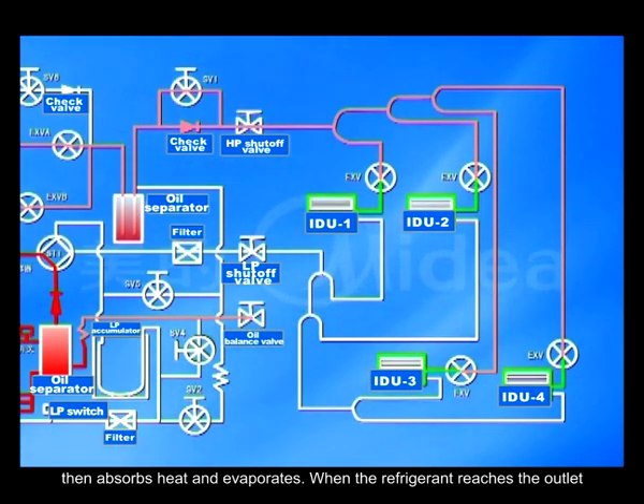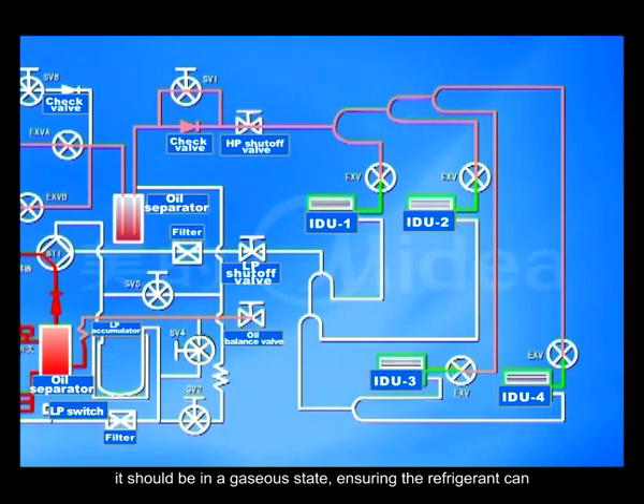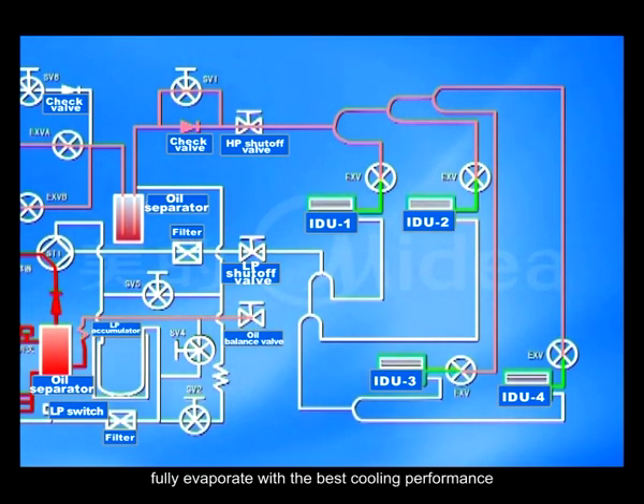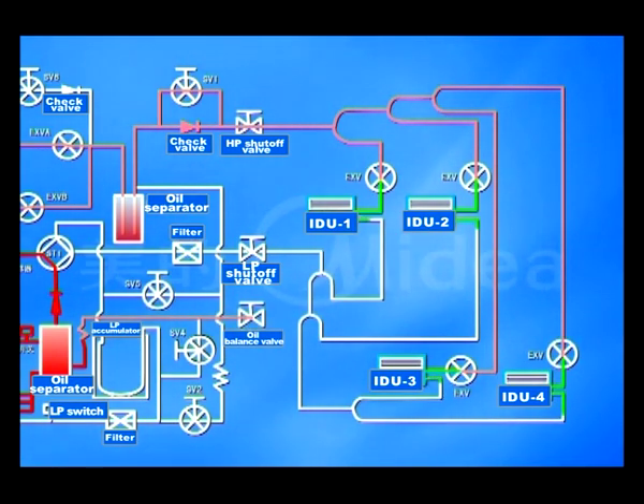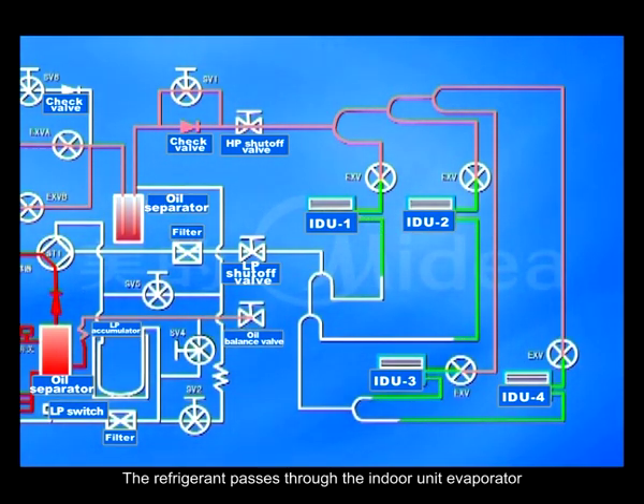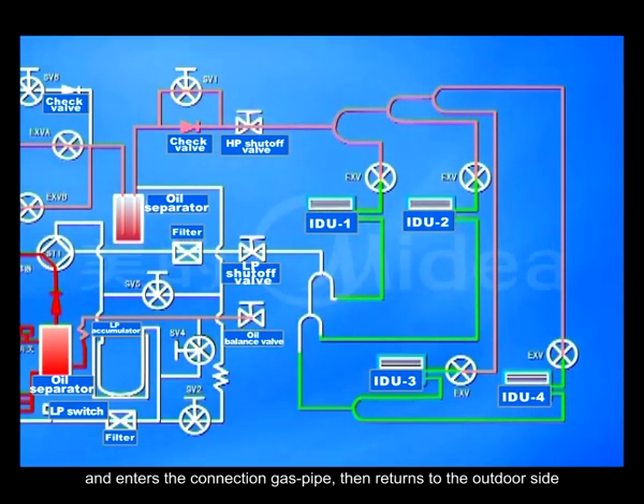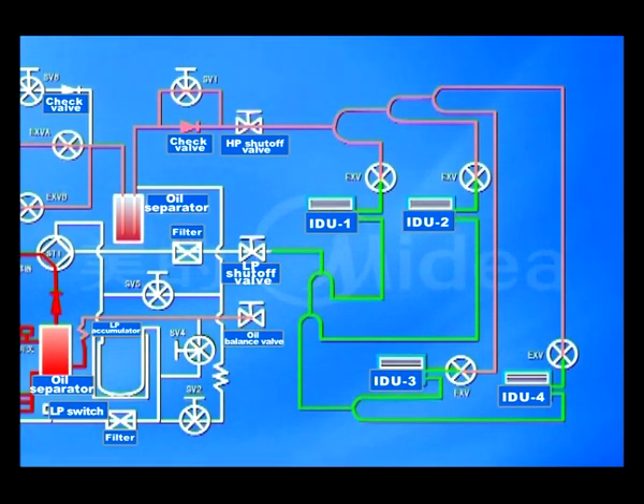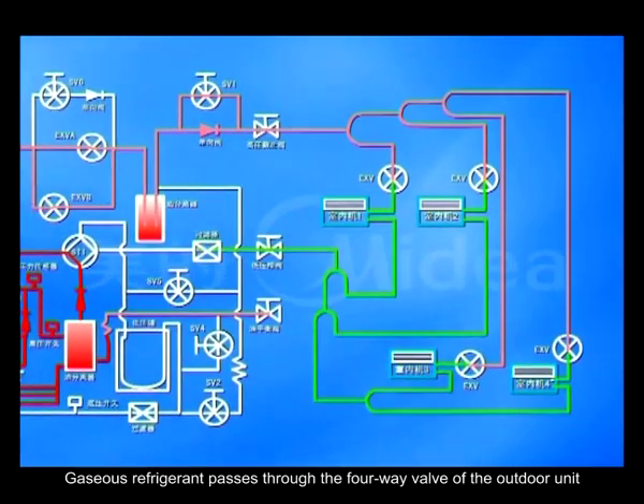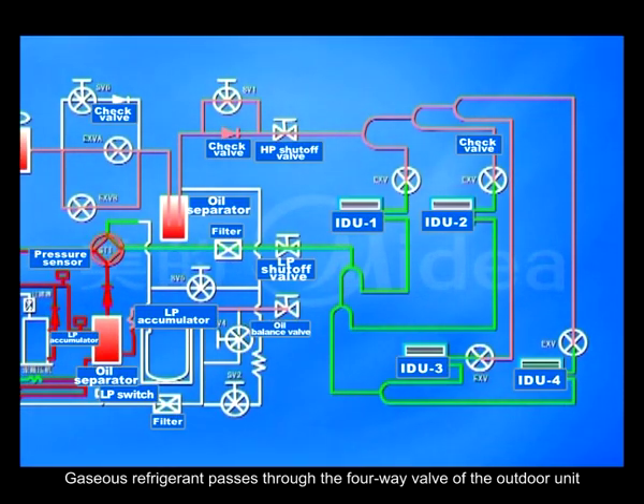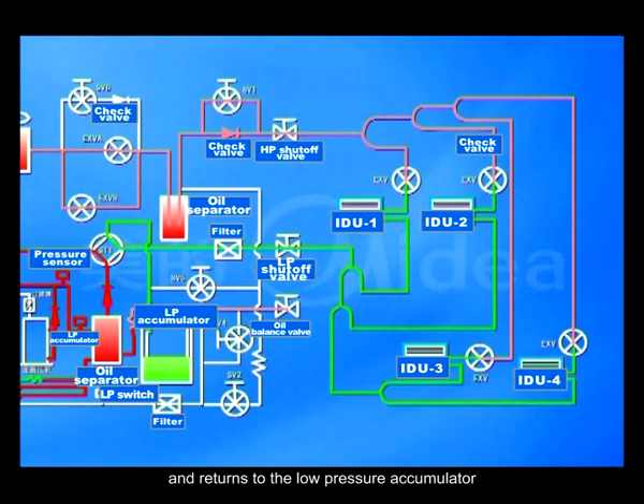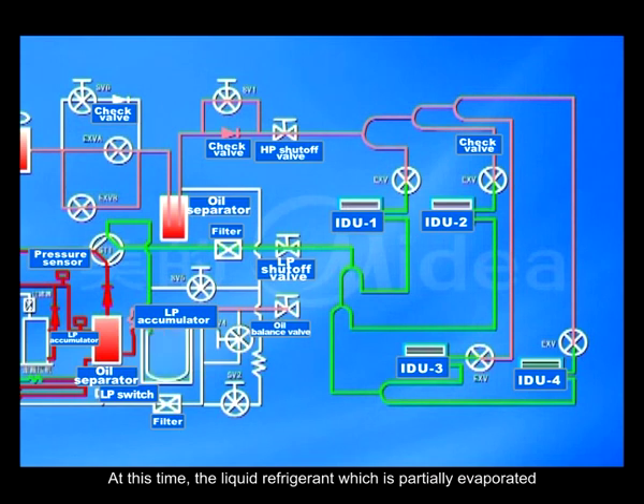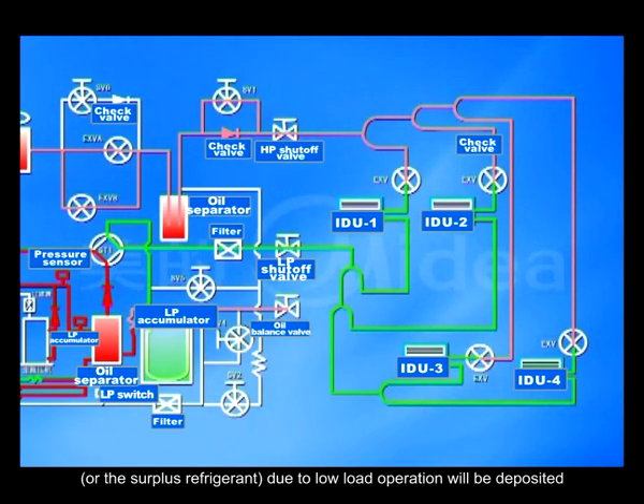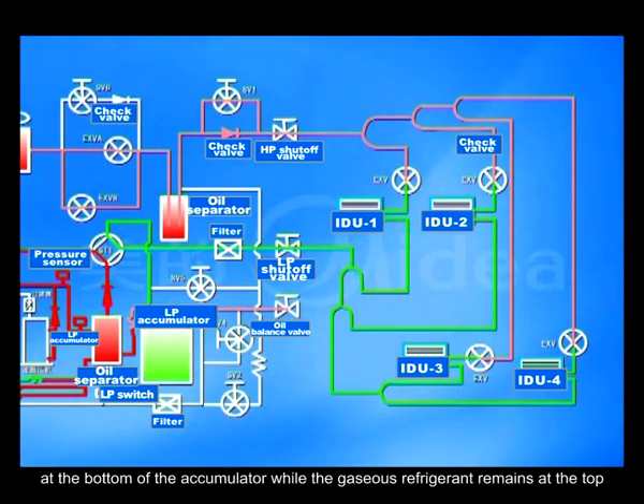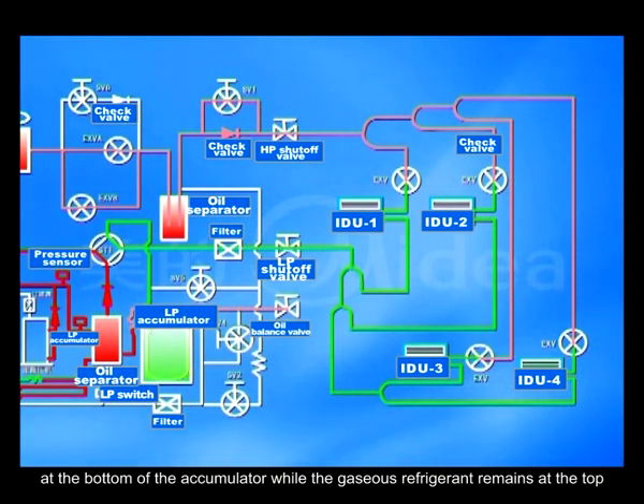When the refrigerant reaches the outlet, it should be in a gaseous state, ensuring the refrigerant can fully evaporate with the best cooling performance. The refrigerant passes through the indoor unit evaporator and enters the connection gas pipe, then returns to the outdoor side. Gaseous refrigerant passes through the 4-way valve of the outdoor unit and returns to the low-pressure accumulator. At this time, the liquid refrigerant, which is partially evaporated, or the surplus refrigerant, due to low load operation, will be deposited at the bottom of the accumulator, while the gaseous refrigerant remains at the top.